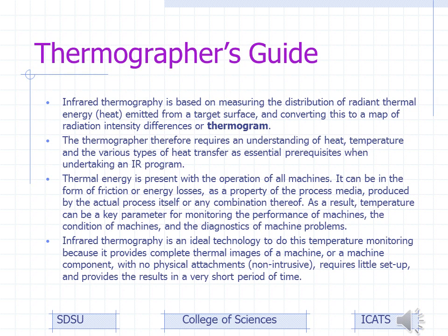If you don't understand the basics of heat transfer or thermodynamics, you're not going to understand where an issue or problem that you see might be coming from, or whether it even is one. A motor gives off heat because of its own internal inefficiencies. Every motor is internally inefficient to some degree, so you're not going to understand why it looks hot. So that's why thermographers need training. That's why there's international standards about that training, so people can understand these specific problems if they haven't had enough physics in college.